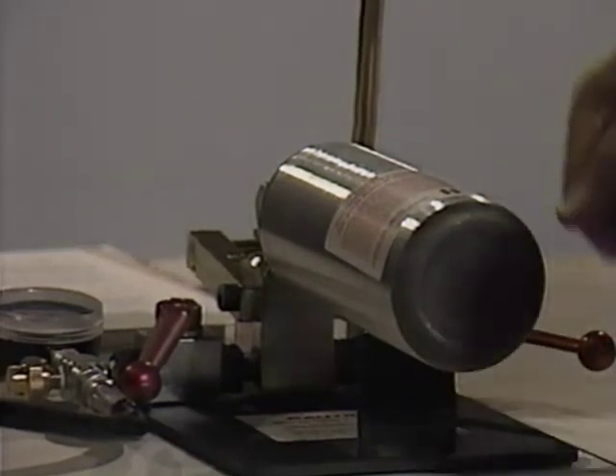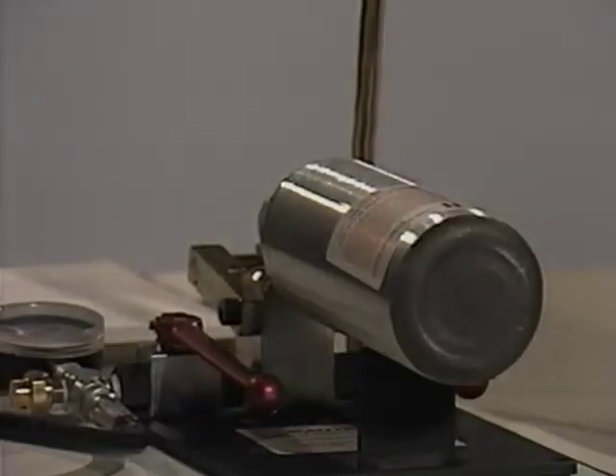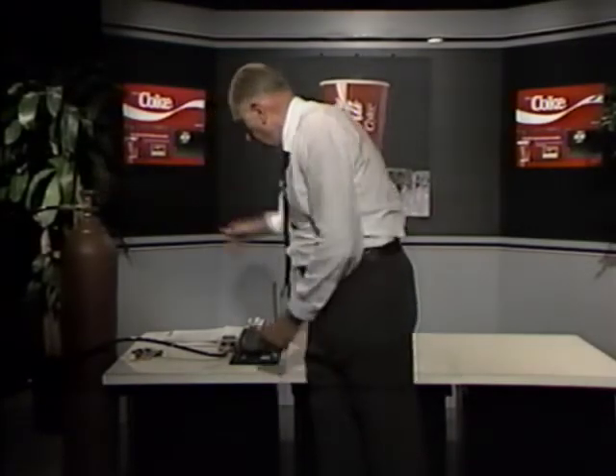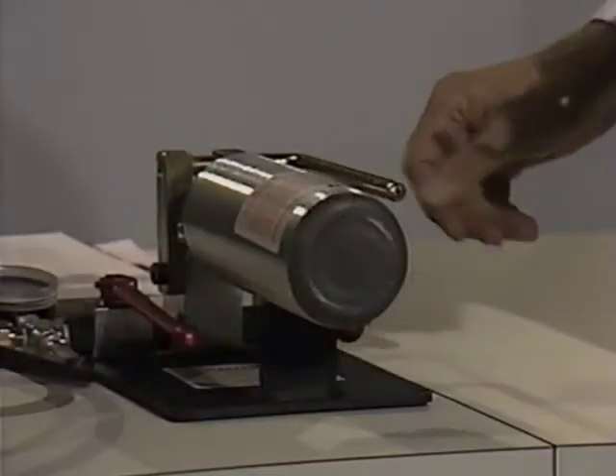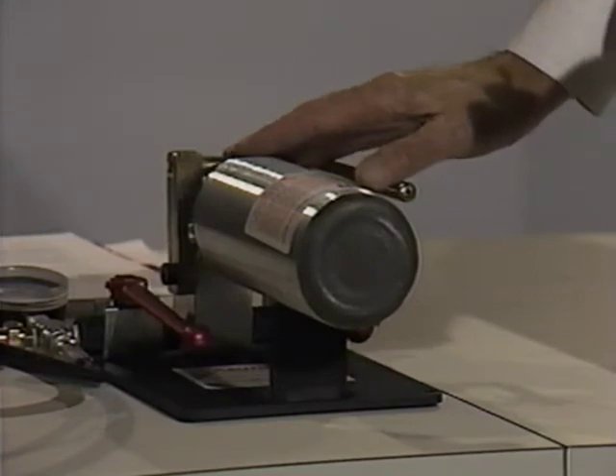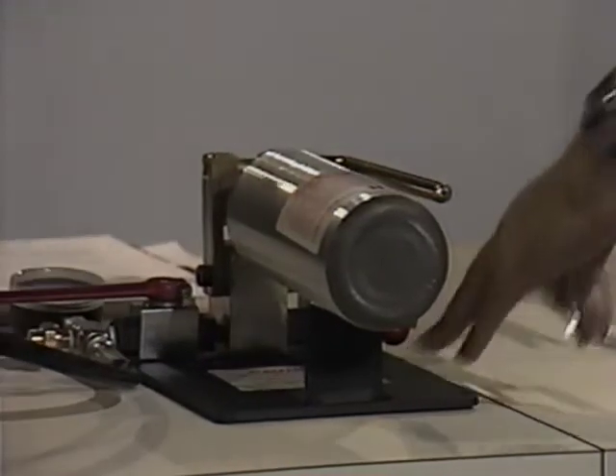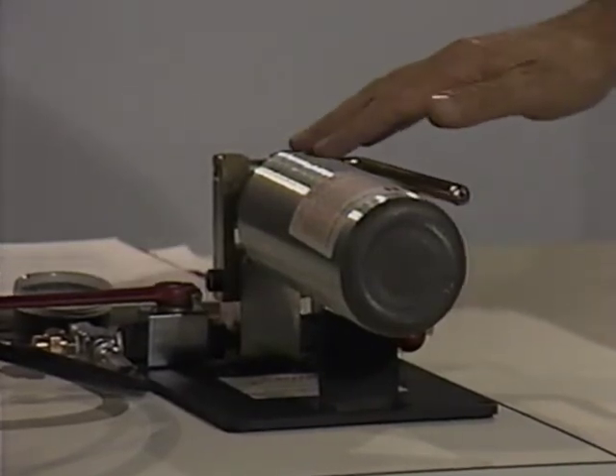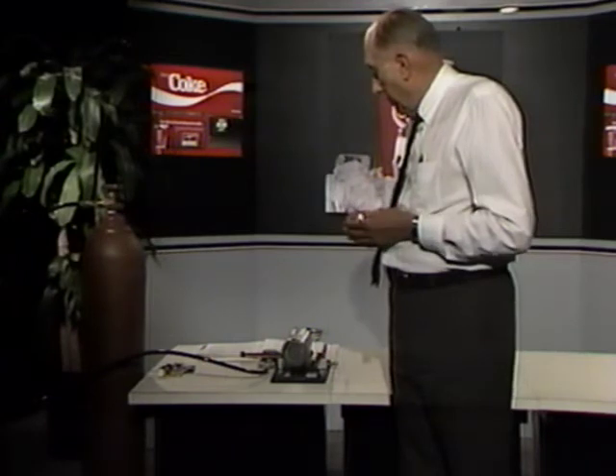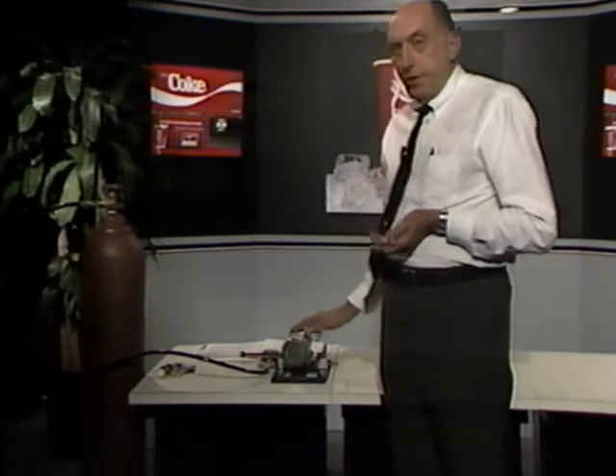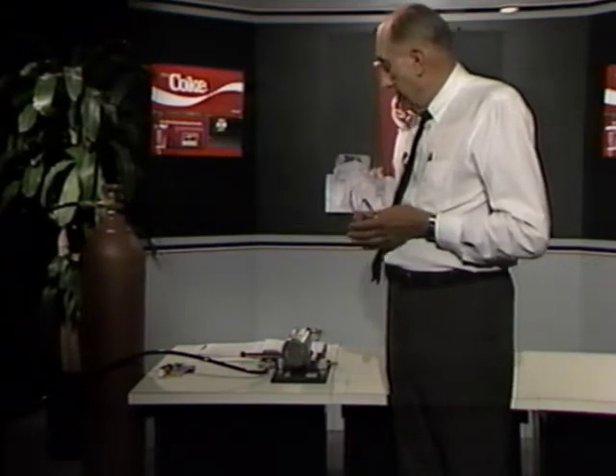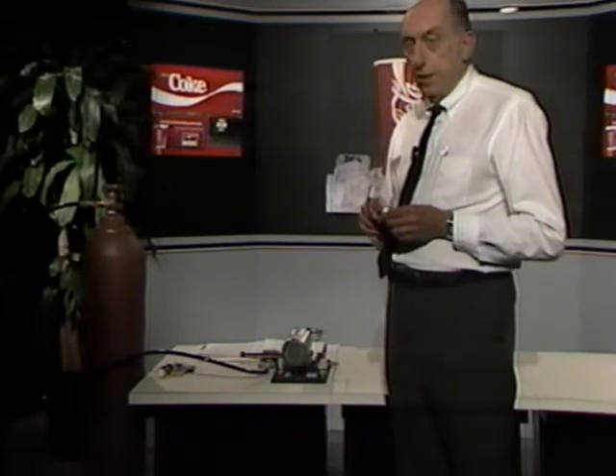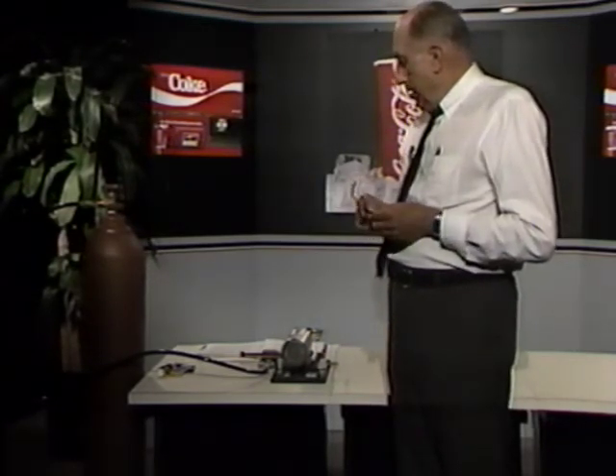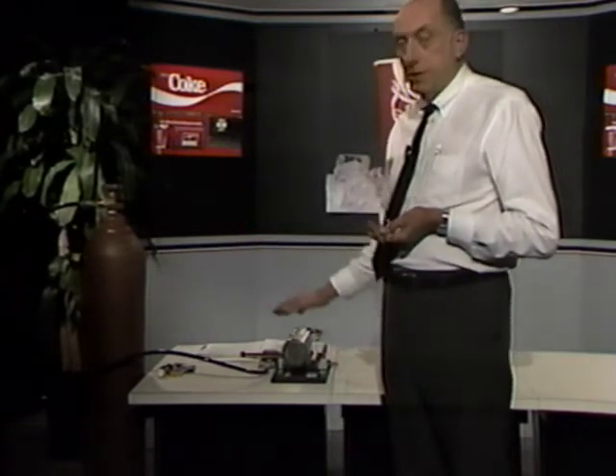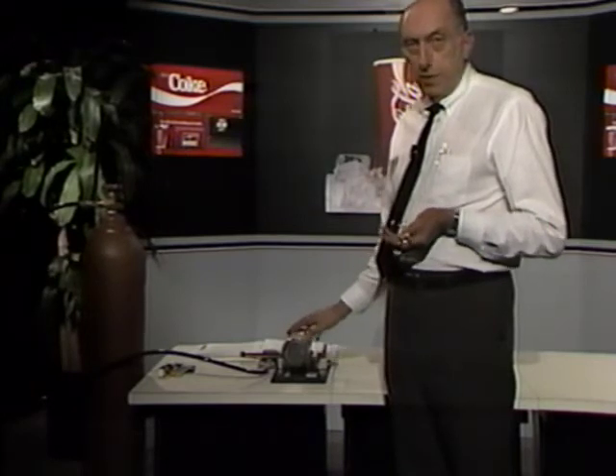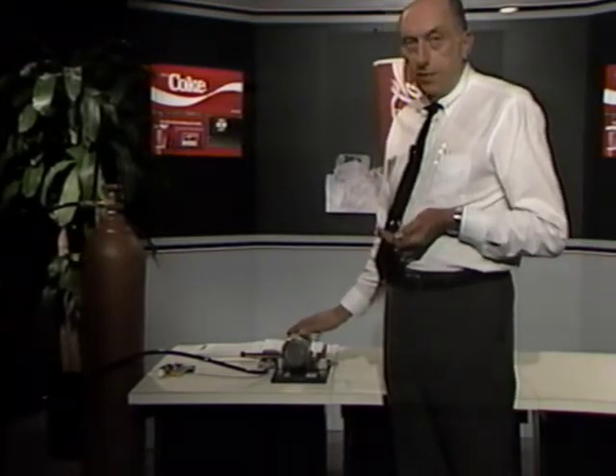You recall we said we would shut off the valves, open the CO2 cylinder valve, put in the small cylinder into the filling head and latch it into position, and then open the inlet valve. And this will permit the cylinder to fill. With the small cylinder cold, 900 pounds in the large cylinder, the filling is accomplished in 45 to 60 seconds. You can listen to the sound that the gas makes when it comes into the cylinder to get an approximation of when the small cylinder is full, as well as using a 45-second timing on it.